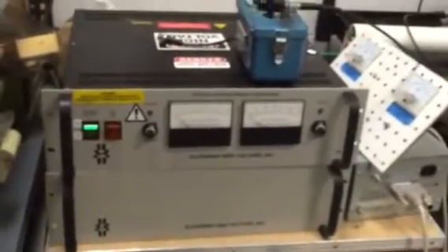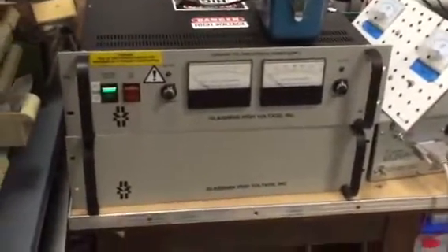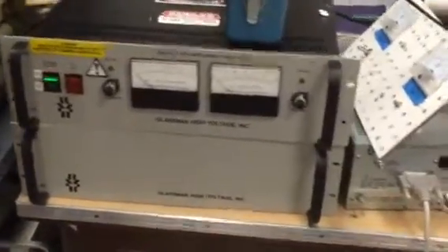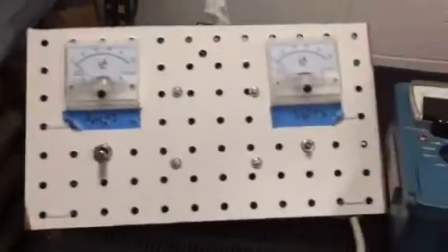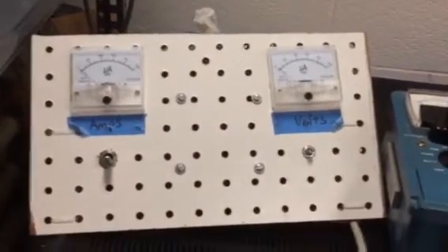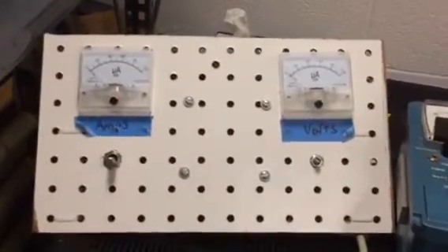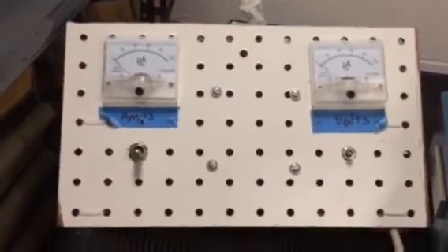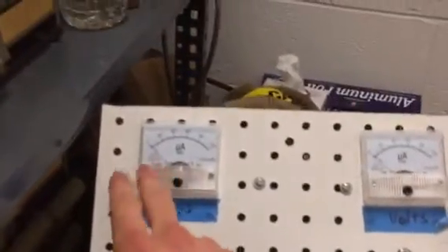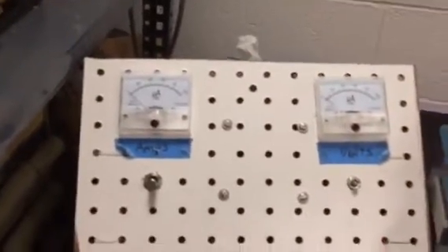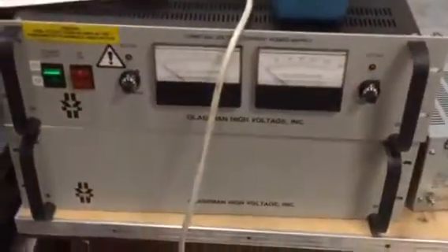For this, we have a Glassman 30,000 volt, 32 milliamp constant voltage and current power supply, and a Glassman 40,000 volt, 7.5 milliamp power supply. This power supply requires a homemade controller, which we have here. Let me just set it down. Basically, this power supply will use an input of 0 to 10 reference voltage, which allows us to completely adjust the output voltage from 0 to 40,000 volts. These panels aren't accurate yet, so for the data we are collecting right now, we are using this power supply.